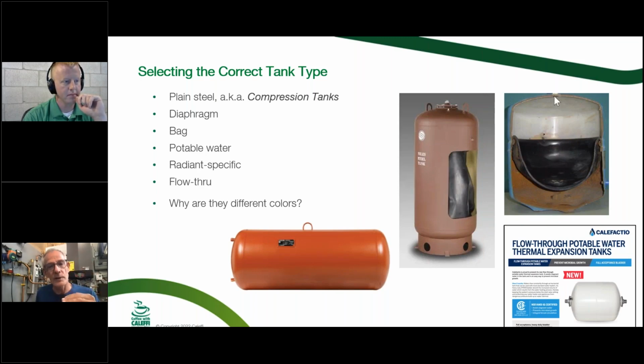In fact, when you put an expansion tank on a system, and you've got a pre-charge to what your static fill pressure is going to be, that bladder is going to be right up against the nipple at the end of the tank. No water goes into these tanks, which is why they can be sized so much smaller than the compression tank, because the only water that goes in there is the expansion water. I don't have to put water in there to trap an air bubble like I do on the plain steel tank. So usually a half to a third the size of a compression tank is what you're going to have on one of these tanks.